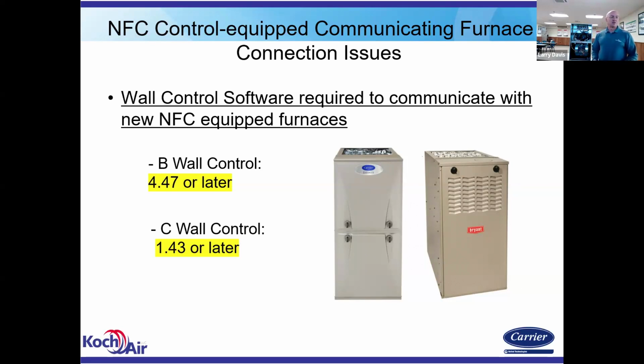Let's see. Question: on a communicating furnace, does it require any of the NFC information to be done if you're setting it up with the Infinity touch control? No. Just like on the previous version furnaces, if you were using it in a non-communicating, you would use the dip switches to configure your fan speeds and all of that. If you are using the communicating wall control, it ignores the dip switch settings and you set everything up through the wall control. It's the same way on the communicating furnaces with the NFC. If you're using the communicating wall control, all that setup is done through the NFC. Good question. Thank you. I blew right past that a while ago.